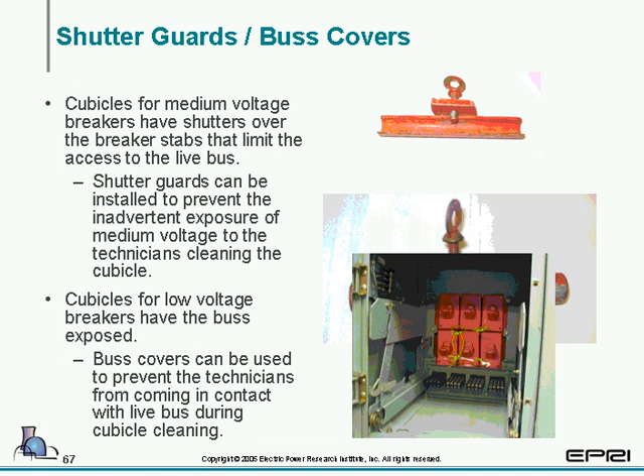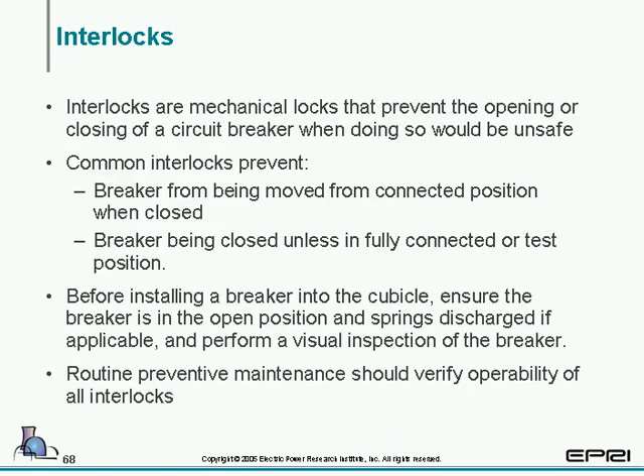On low voltage switchgear, 480 volts and such, you have bus covers that can either be provided by the manufacturer or can be purchased or even fabricated. Bus covers such as these used on low voltage prevent technicians from coming into contact with live bus during cubicle cleaning. I do realize we have a question on getting into the cubicle. We'll try to address that toward the end of the session here.